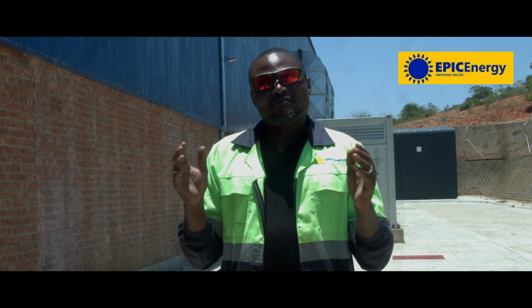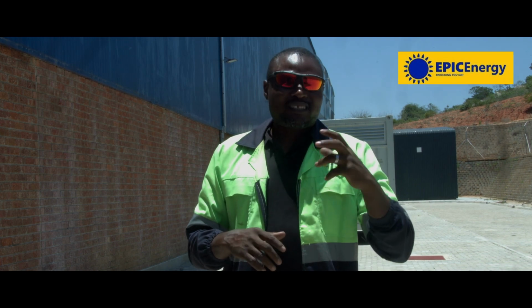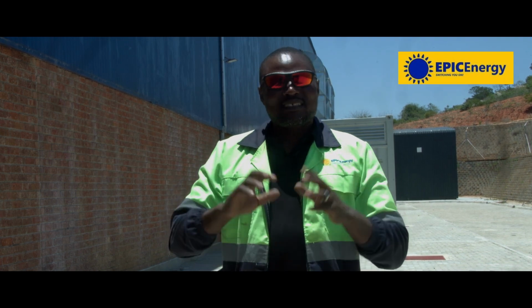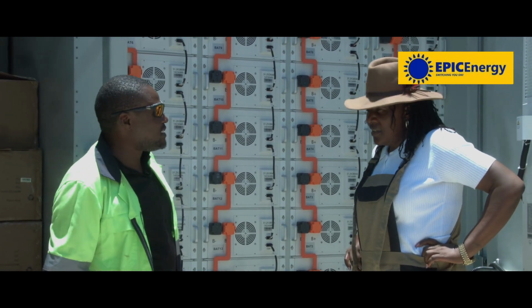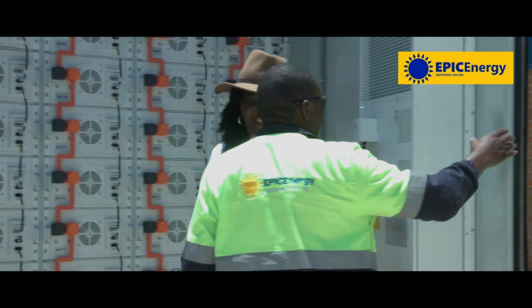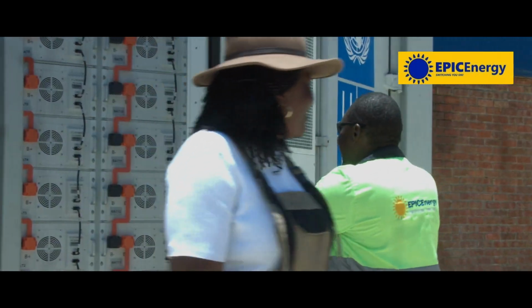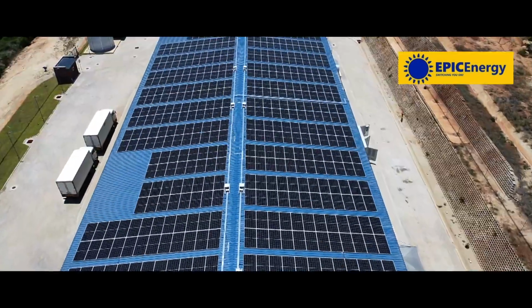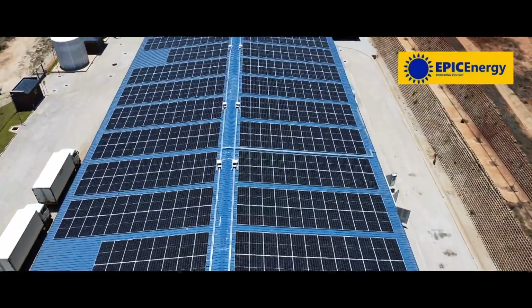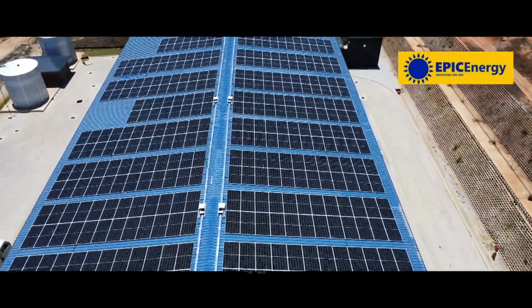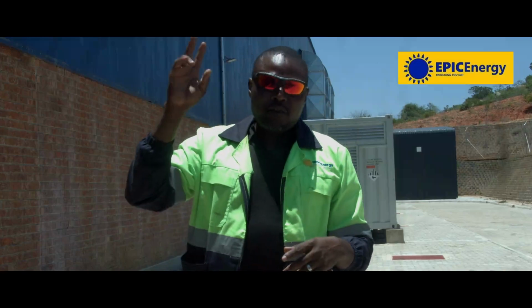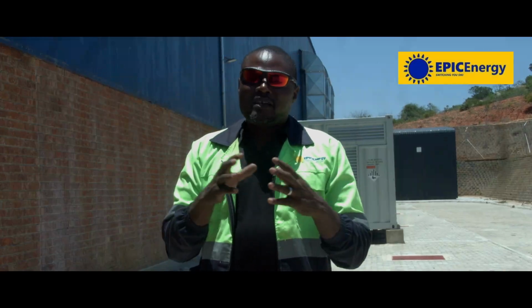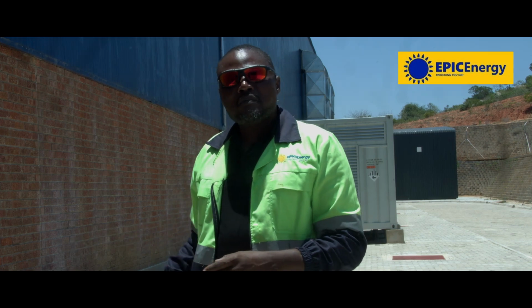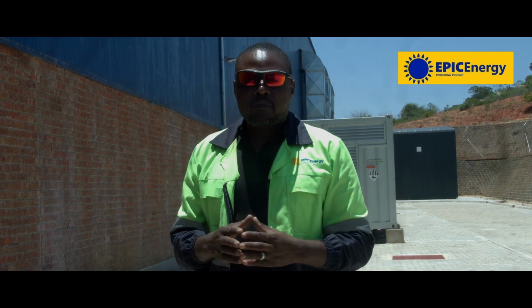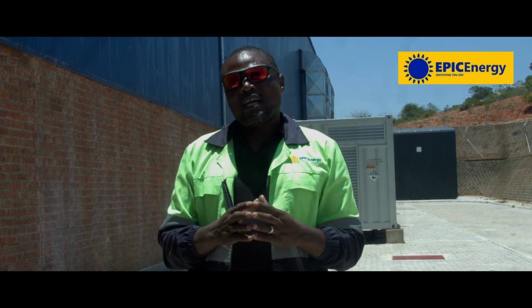So it's a complete unit for safety, for protection of the system itself, and in case of those scenarios where there are fires. From the surge protection and the combiner box, it comes down into our MPPTs. Each combiner box is holding 5 strings of 16 panels which are connected in series, and they are combined in the combiner box. I think we have a set of 9 combiner boxes. Then from the roof it comes down into our MPPT. We have 9 strings going into our MPPT that add up to the capacity that I've just mentioned.